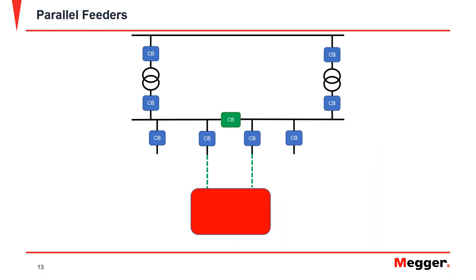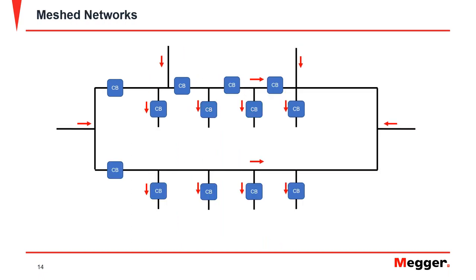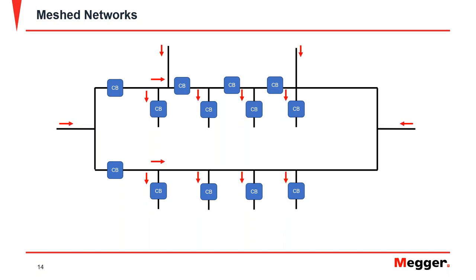Parallel feeders are used to supply important customers where continuity of supply is critical. More than one feeder supplies the customer so that if power is lost in one, the other can supply the load. Mesh networks allow more than one injection point of power into the system. These are harder to protect and design, but much more reliable when it comes to continuity of service.